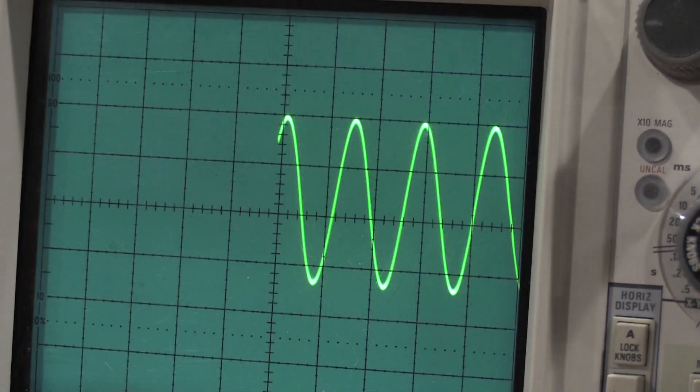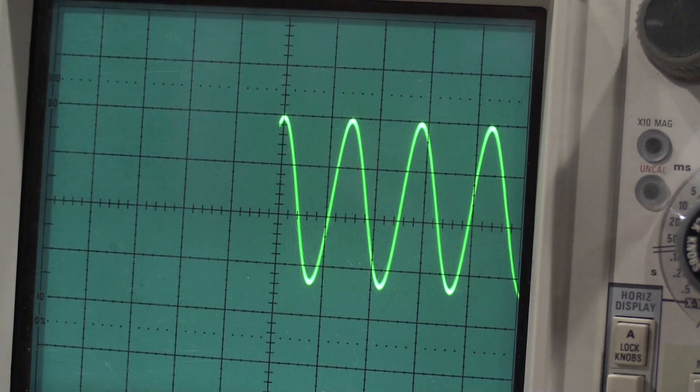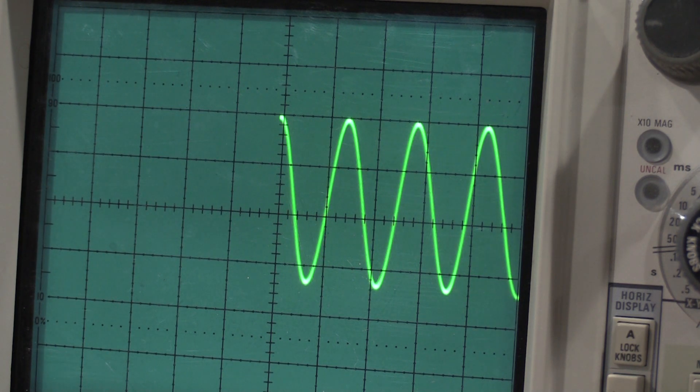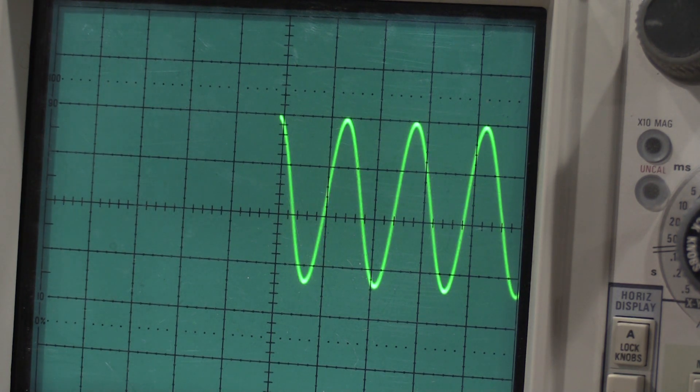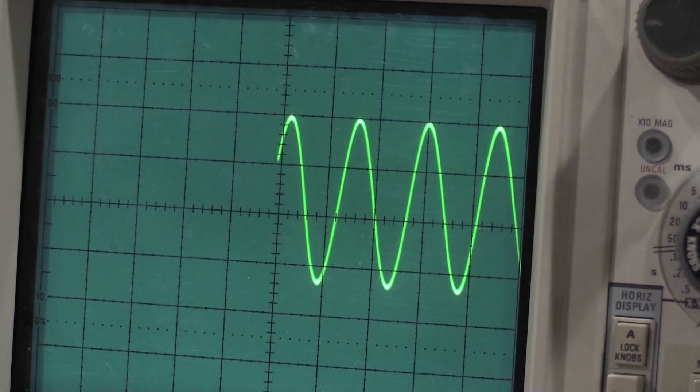In adjusting the sensitivity, we have a maximum of 0.2, which is what we're looking for. Our R565 was out just a little bit, not horribly. So now what we need to do is test to make sure we don't have the trigger too sensitive.